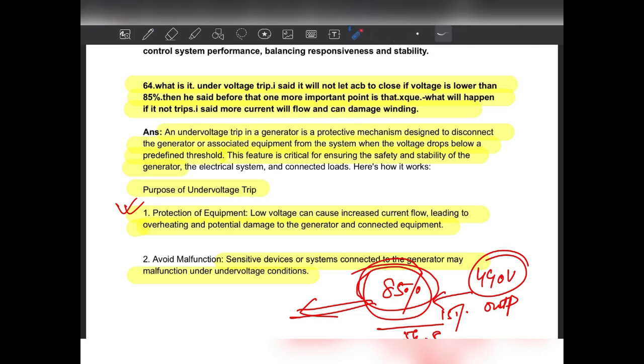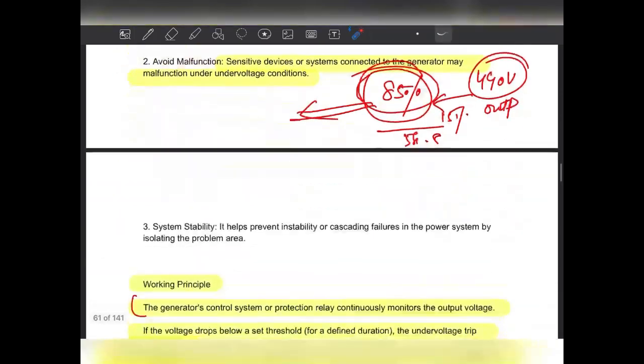And here is a question. I said it will not let it close if the voltage is lower than 85%. Then he said, before that, one more important point: what will happen if it does not close? Let's suppose your ACB is not opening, the under voltage trip has already happened, your voltage is below the set point, but your ACB will not let it open. So what will happen at that time? Due to this, more and more current will flow and damage the winding. So this will happen. Okay, so you have to read this one.